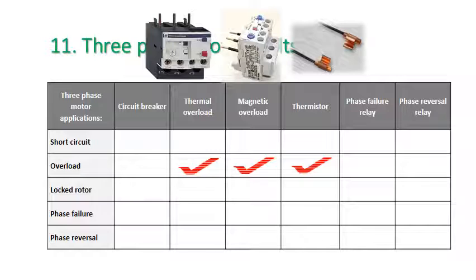The one advantage of thermistors is that they're going to notice temperature rise for whatever reason. There might be blocked vents in the cooling of the motor or something along those lines. The thermistor is still going to pick that up. The disadvantage of thermistors is they're difficult to test to see if they're actually working. You'd have to heat the whole motor up and monitor the thermistor, so that is an issue. The other thing is that they are susceptible to being insulation resistance tested, and you can blow them up, and if they are broken, it's difficult to replace them. You have to get into the windings of the motor. You probably need to send it to a motor rewinder.